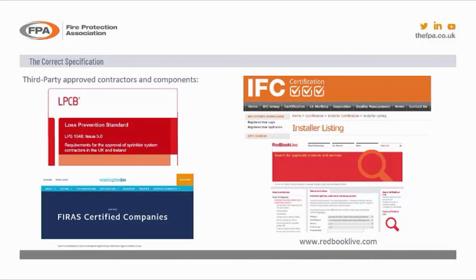Selection of third-party approved contractors. Not only third-party approved contractors, we've got sprinkler components as well. So it is essential in confirming their ability to deliver a sprinkler system that your contractor is a scheme member of one of the three. So we've got the LPCB that runs the LPS 1048 scheme. We've got FIRAS, and there is now the IFC, the International Fire Consultants Certification Scheme. All three companies ensure quality of service and meeting compliance to standard.